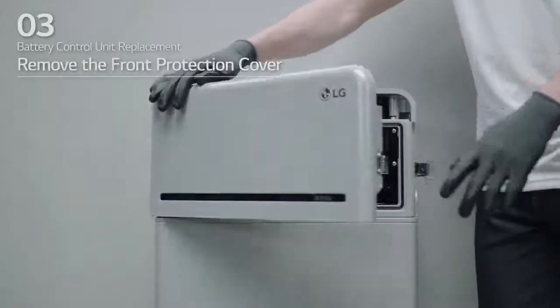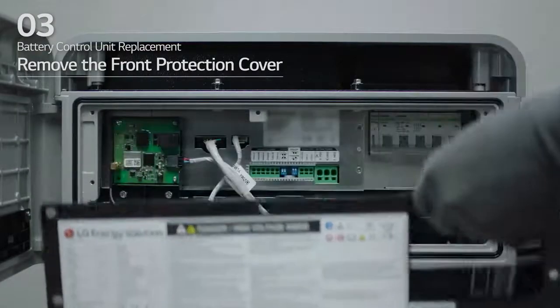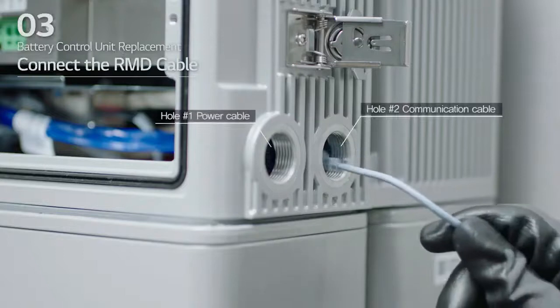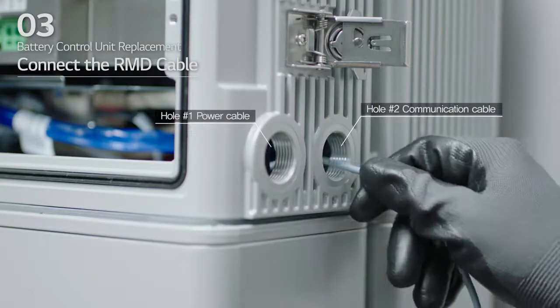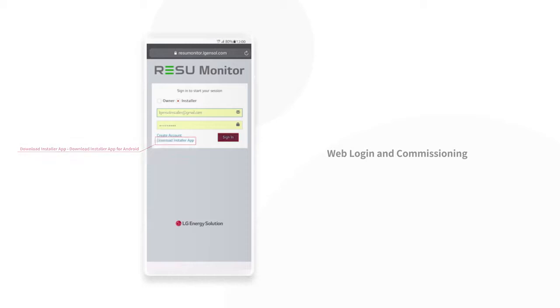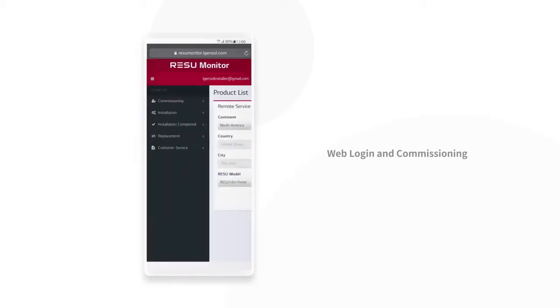Open the front cover and loosen the 6 bolts to remove the front protection cover. Insert the RMD Ethernet cable through hole number 2 and connect the cable. Then, you should complete the RESU Monitor setting with these steps. First, visit RESU Monitor site and enter your ID and password. Access Commissioning on the left sidebar. Select Create Commissioning Info and fill in the information.